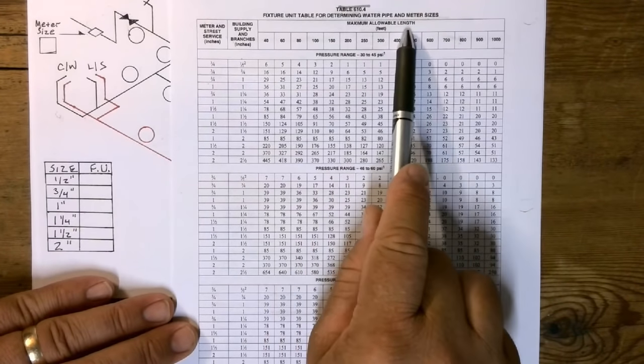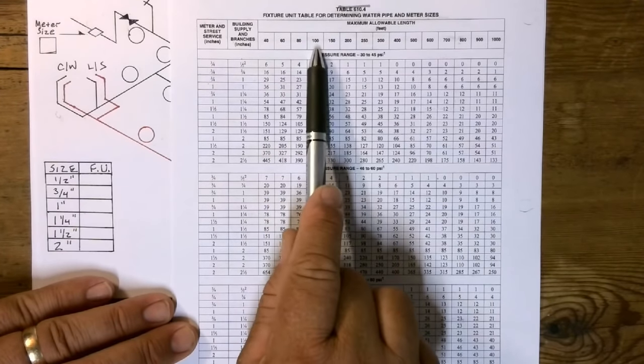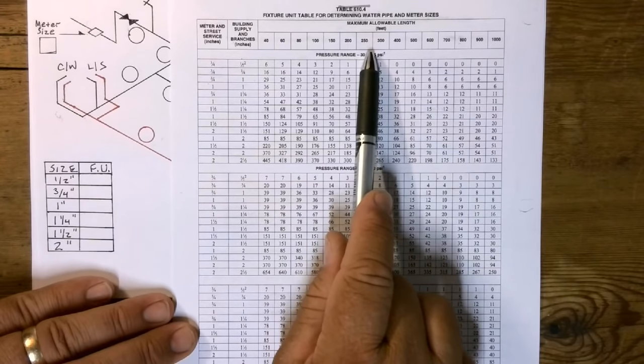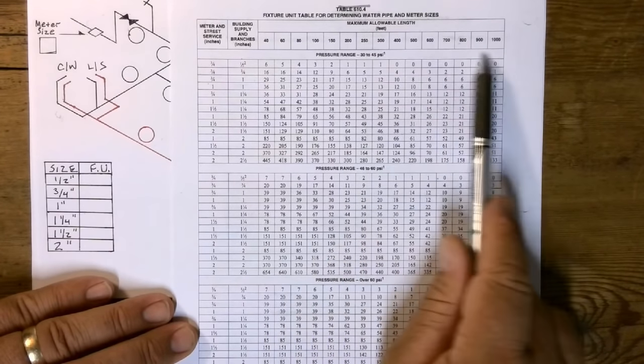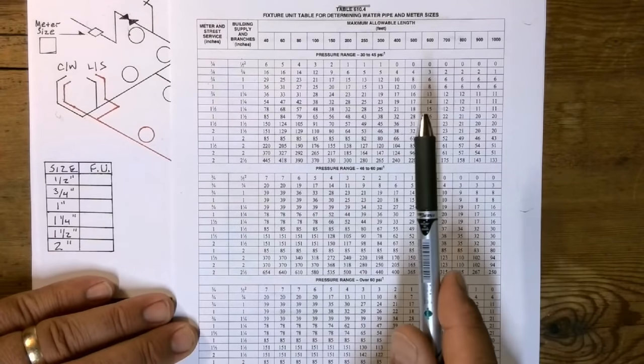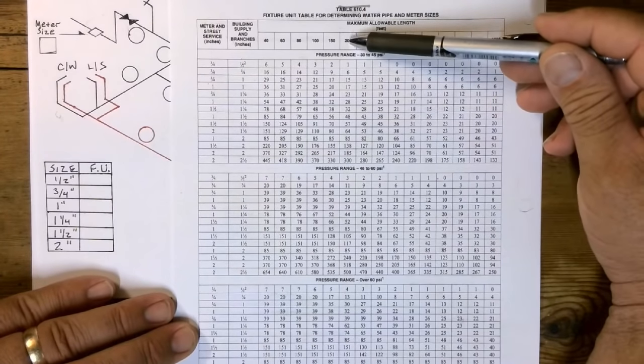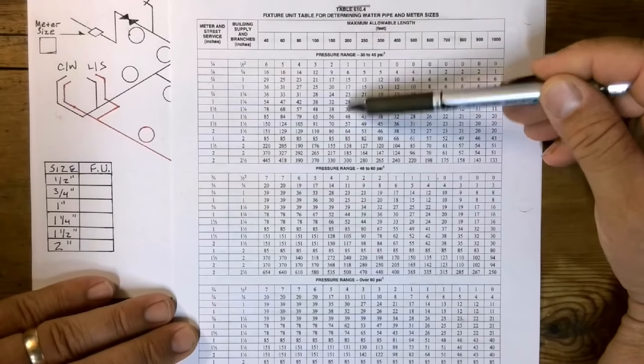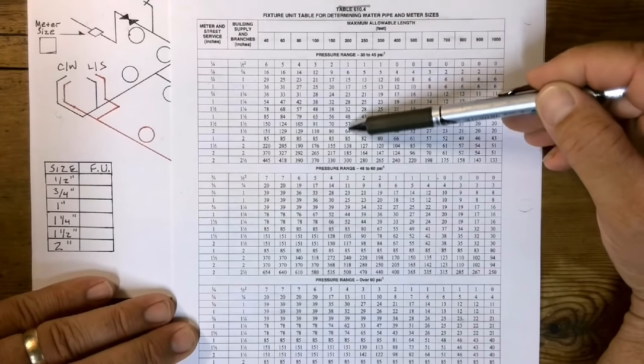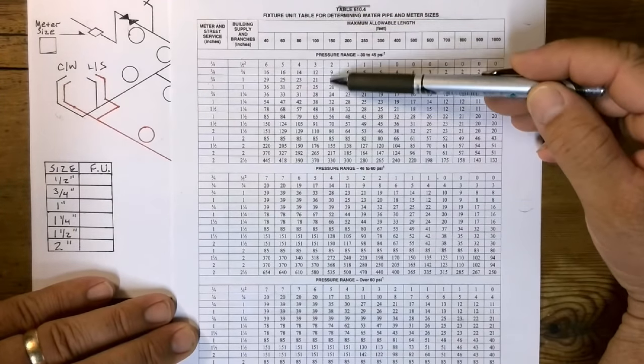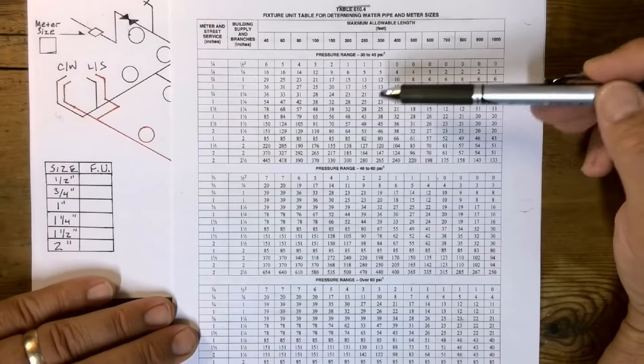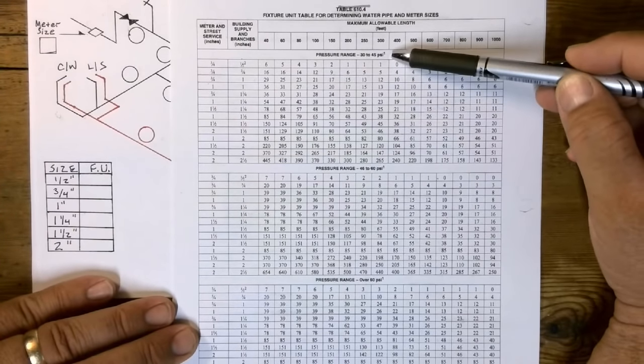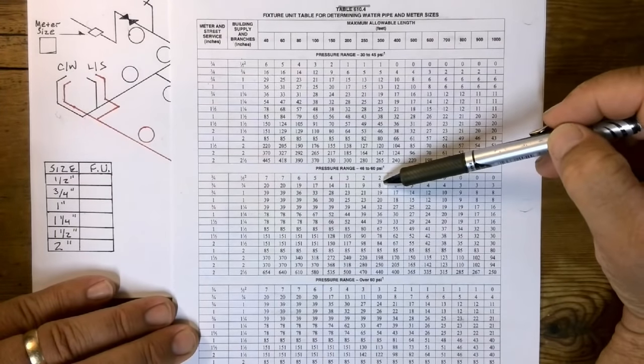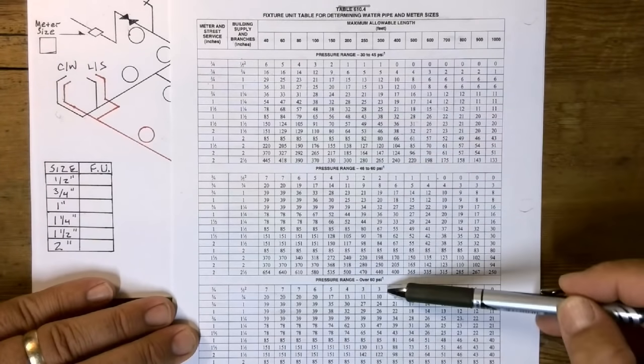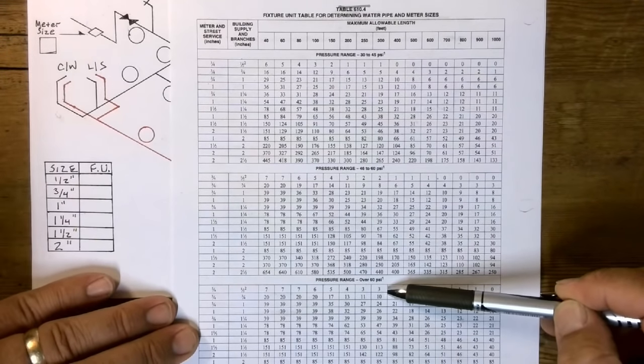Quick rundown. This is your maximum allowable length: 40, 60, 80, 100, 150, 200, 250, 300, 400, 500, and so on. So this is the column that we're talking about. 200 feet goes in this column right here. 150 feet goes down this column right here. But check this out. I have a pressure range here between 30 and 45, a pressure range here between 46 and 60, and a pressure range over here over 60.